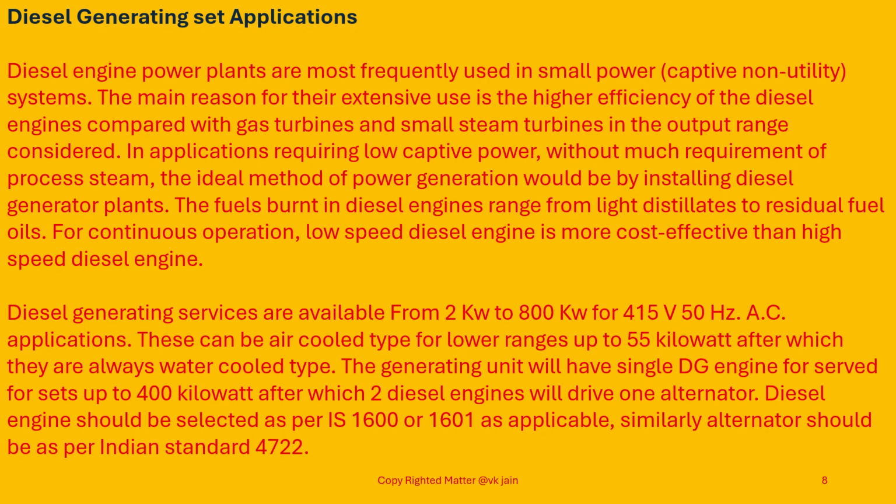In applications requiring low captive power without much requirement of process steam, the ideal method of power generation would be by installing diesel generating plants. The fuel burnt in diesel engine ranges from the light distillates to residual fuel oils, normally HSD, high speed diesel oil, and LDO, light diesel oil.